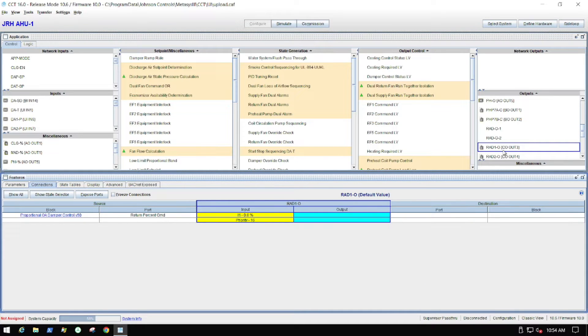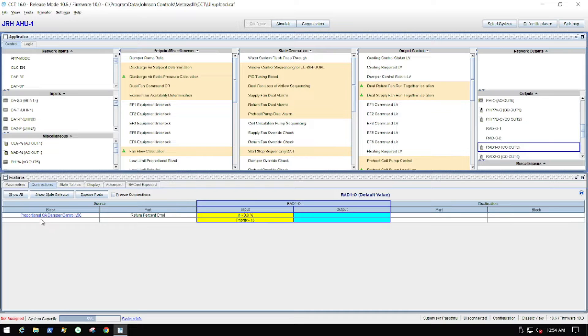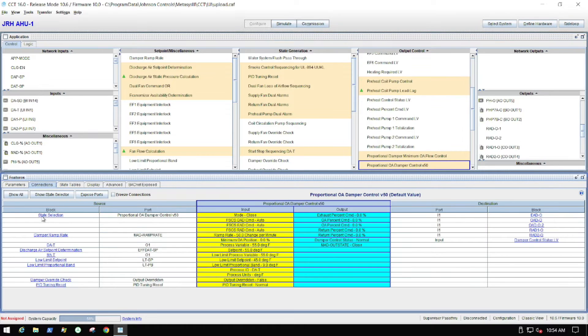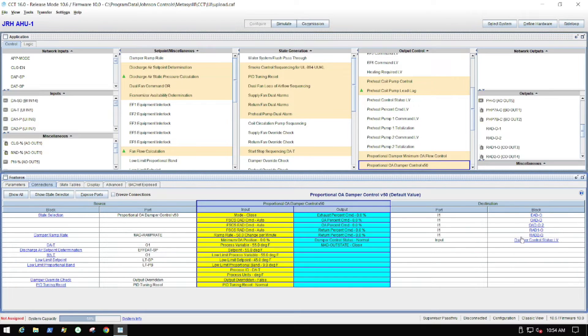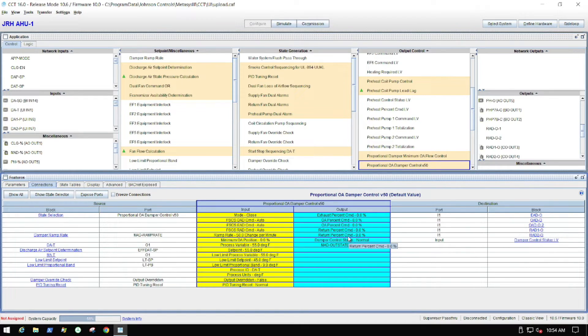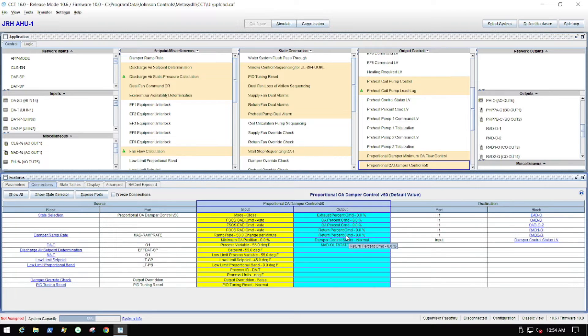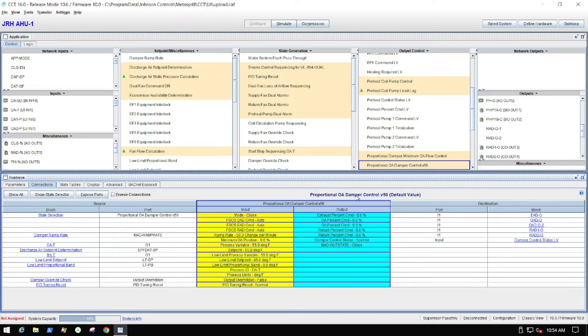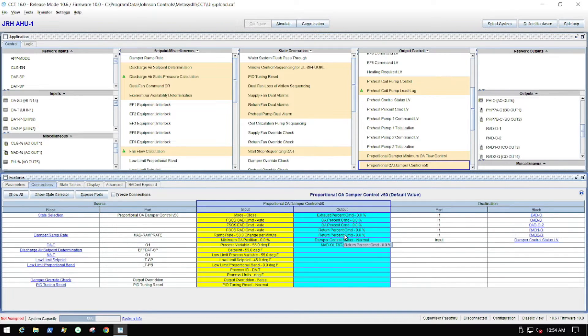So once I highlight that, it's going to give me the connections tab. You know, I can see it down here below. And then when I select the logic block, it's going to put a ribbon around it. It's going to give me the options here that I need. And here is where I'm going to make my connections. I'm simply going to go to where the original logic point is connected to the existing points. And then I'm going to make a new connection.